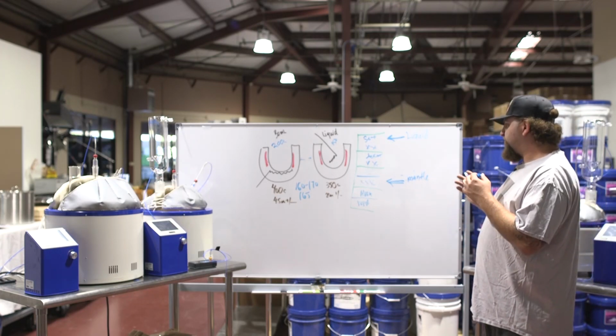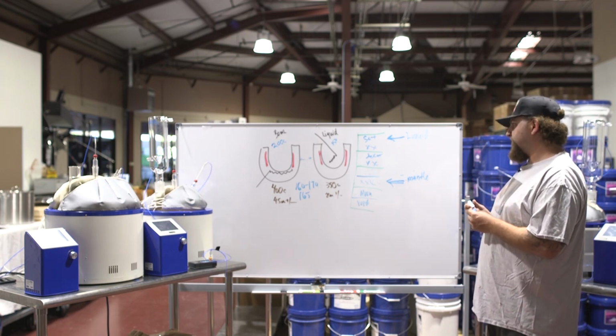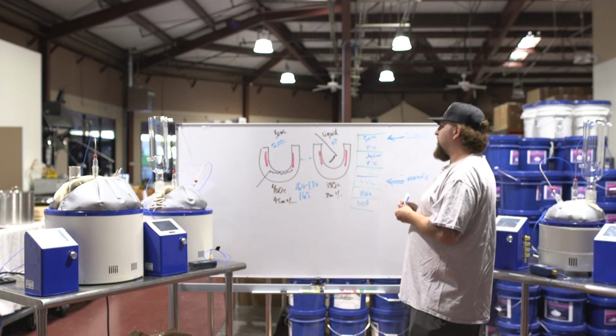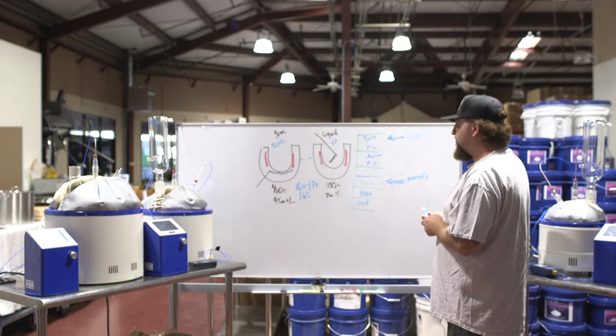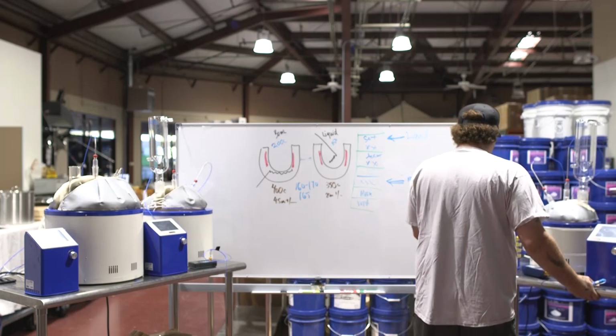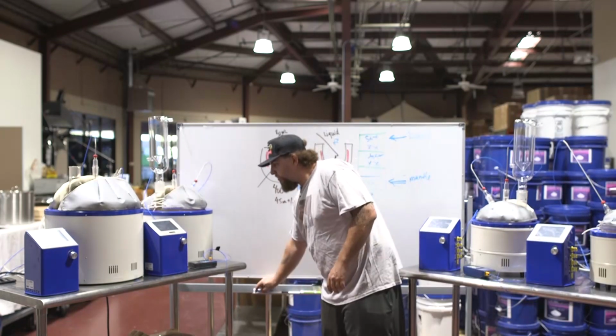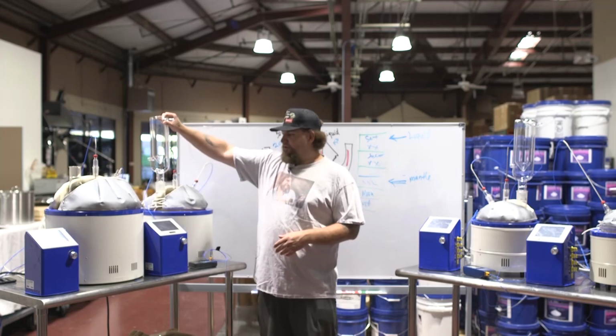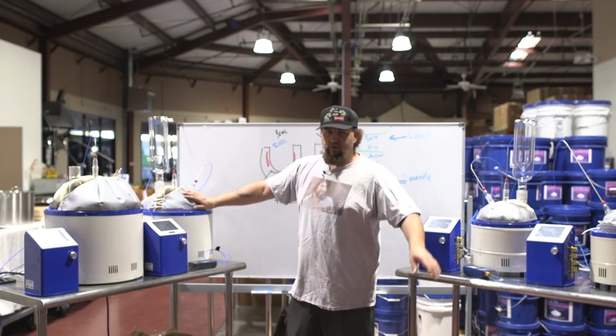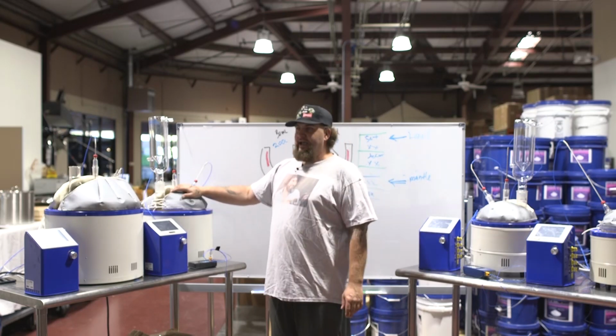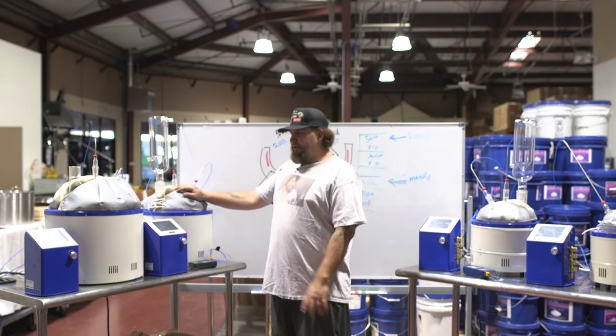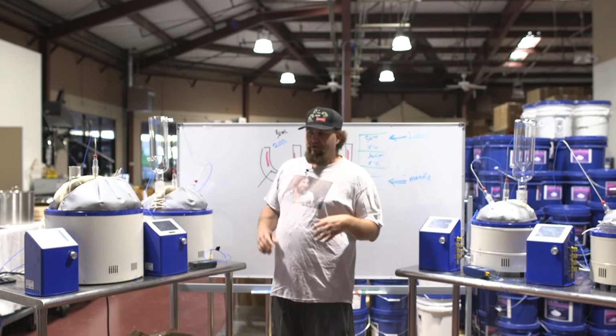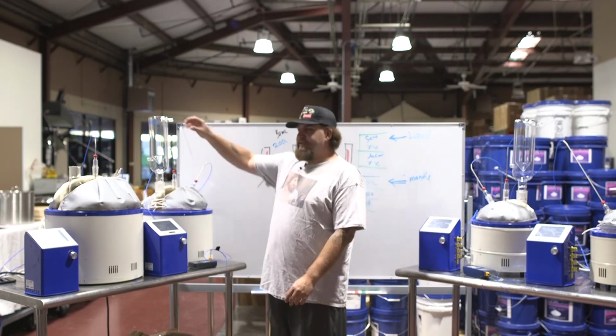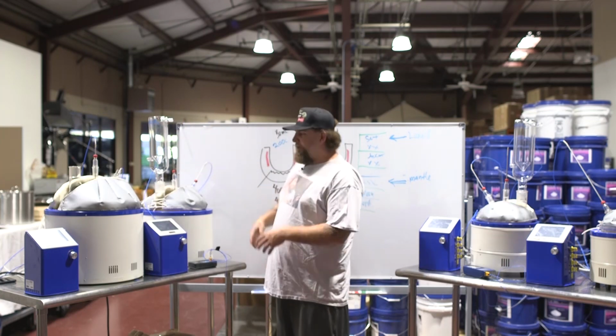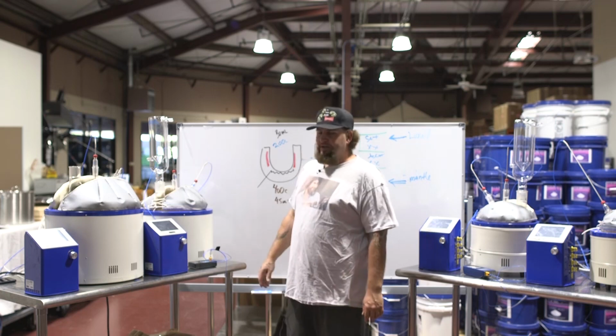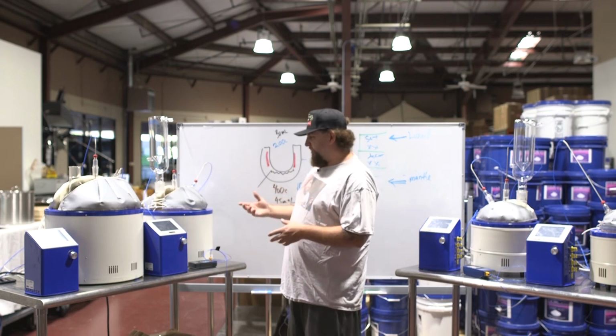So now people always want to say, well, how do I calibrate this to my needs? I really think personally, the liquid side is going to be the easiest one. Now, I'll just use both of these as an example of how I would do it. I would take a cold trap and I'd use vacuum pump oil on a brand new flask. You can reuse the oil, it doesn't go bad, it actually cleans it up when you do this. There's about a half a cup to a cup of water, sometimes an average amount, I'm not really sure, but there's quite a bit in there, and that creates a reactive oil, so you want to pull vacuum on the system. I just take a basic cold trap, throw it on this. In this instance, to do my calibrations, we have a different setup here, but I'll explain what you would do normally.